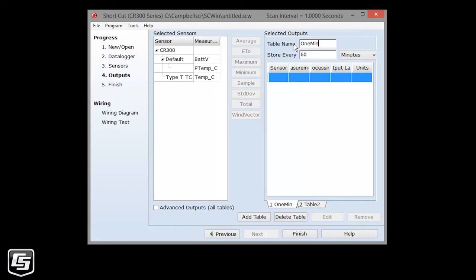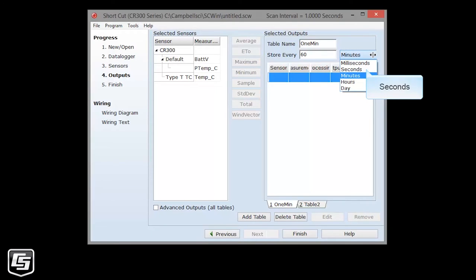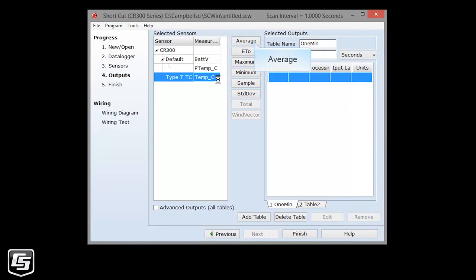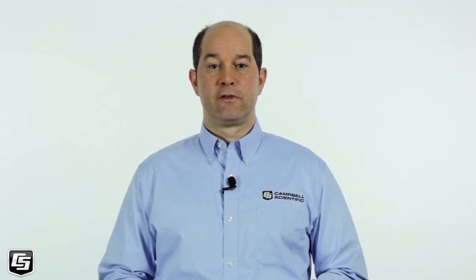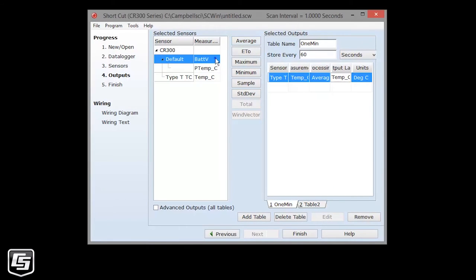In this example, you'll want to store data every one minute or 60 seconds. Since the interval is 60, choose seconds as the units. Or you could have changed the interval to 1 and use minutes. Now we'll add measurements with processing to the table. Every minute, we'll have the data logger store the average air temperature. Since the data logger is taking one second measurements, this will be an average of 60 discrete measurements. Other measurements and processing are added in the same way.